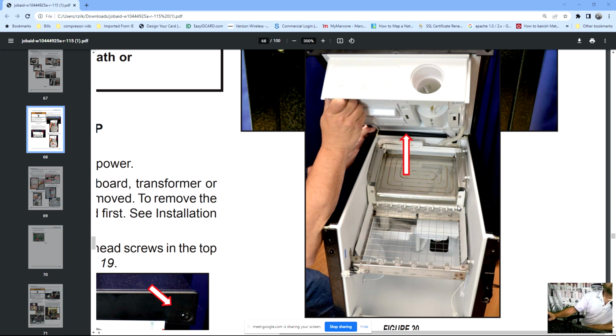Okay, so here's the cutter grid. This cutter grid is low voltage, and we'll talk about that when we get to the schematics. And this is the evaporator. Now notice these lines on the evaporator. Those lines are the actual refrigerant tubing underneath, and they electrically weld it, like arc weld it, to the underside of the stainless steel plate.